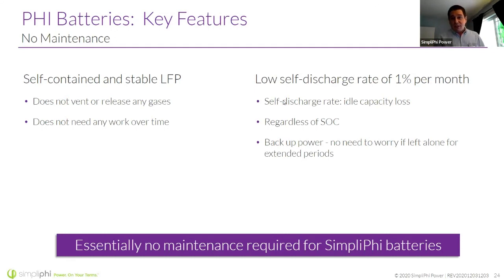Another feature is that they're not terrible to just sit around for a bit. They're going to discharge at about 1% a month, a relatively low self-discharge rate. We'd caution you that this is constant. We ship our battery at roughly a 30% state of charge, so if you get a battery, you don't want to let it sit around for 3 years, because that could self-discharge below 0% capacity. If you're going to let a battery sit around, we'd recommend charging it maybe once every 6 months, or at least making sure you top it off before it goes into storage. That gives you some time to get to installing it.